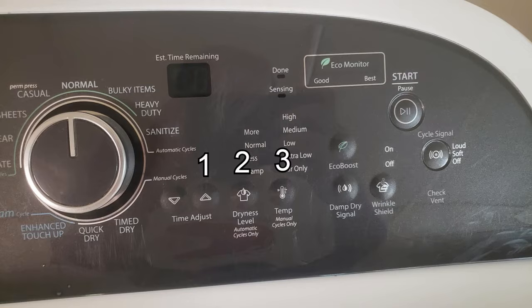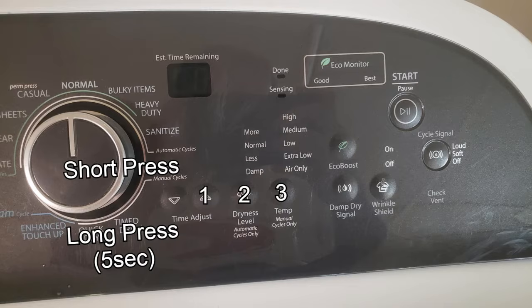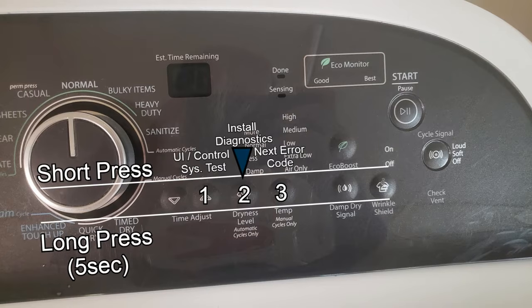Once in diagnostics, every single command gets issued from the number on the button that you pressed when you put the machine into diagnostics. So I've labeled them 1, 2, and 3. Depending also on how long you press the buttons, it will change the option that you'll select and go to. Do note that the long press takes at or over 5 seconds, so it's unlikely you're going to access the wrong thing.